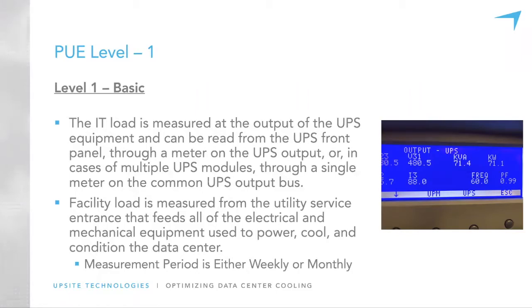PUE level 1, 2, and 3. I want to talk about all of these very quickly, and then I'll show you how they can be used in a live data center. So if we go to PUE level 1, this is a basic measurement, and it's measured at the output of the UPS system. The picture I have up here is from a very old UPS system. It's a 9315, but we have an I/O board on there that's pretty standard, and most UPS systems, I have not seen one where it does not have an I/O board where you can read the output. And that's where we would start to get our baseline measurement information for a PUE level 1 reading.